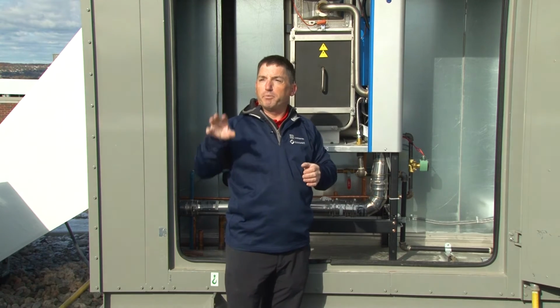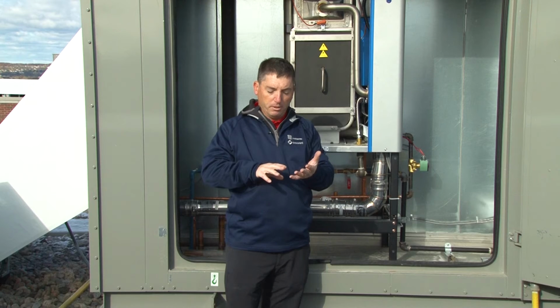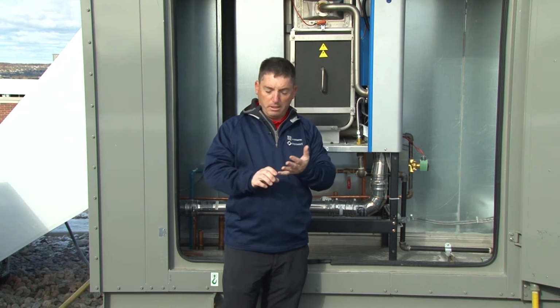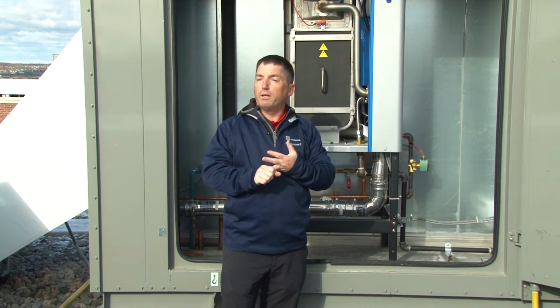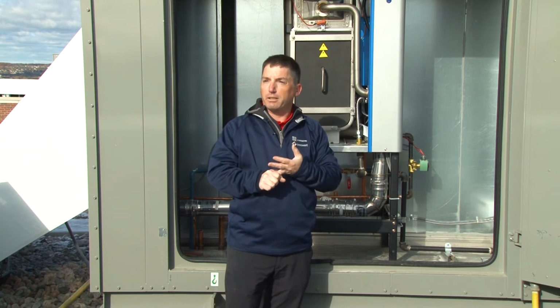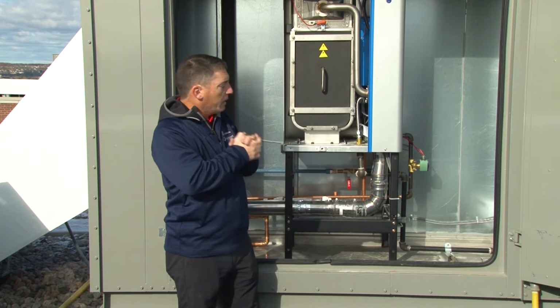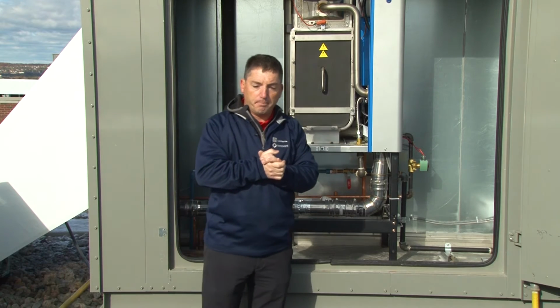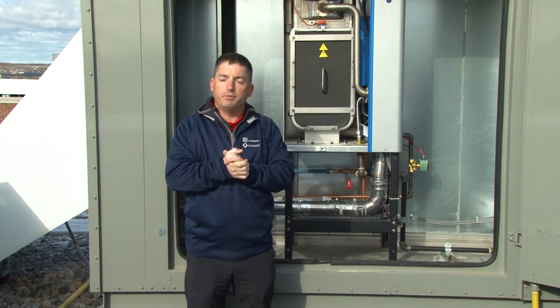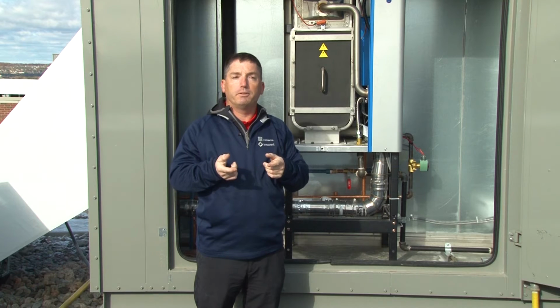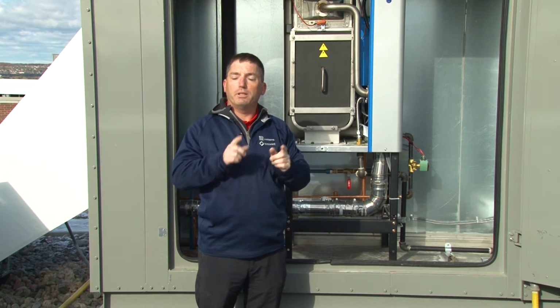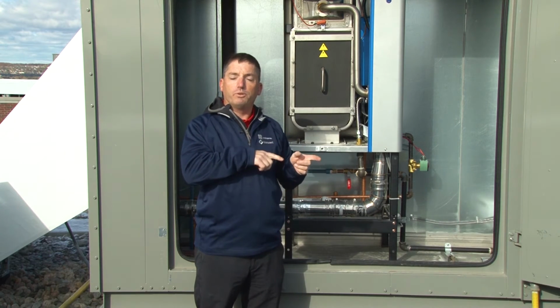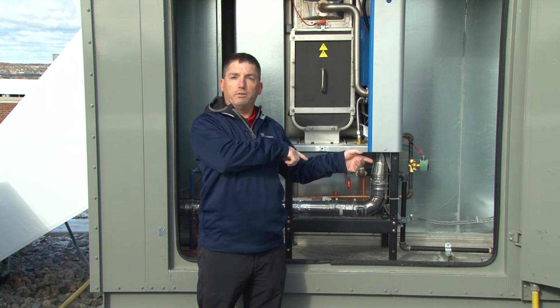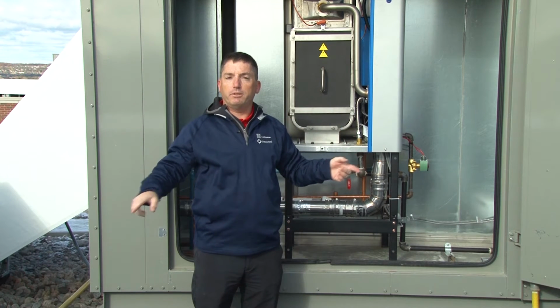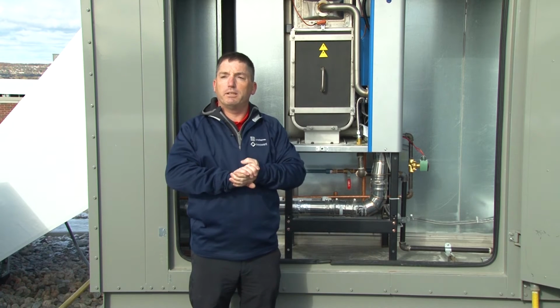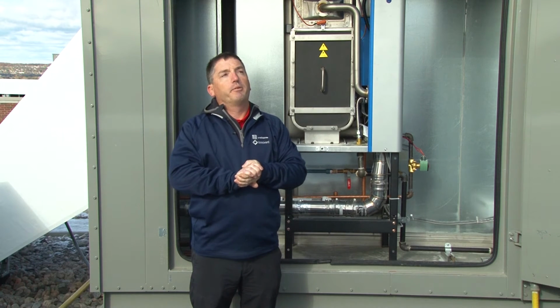It's actually going to bring up the full written description of what the code means and what possible remedies are for fixing that code. The gas unit does have internal timers, if you will. So after a couple hundred hours, it's going to close a contact which will send a signal to the keypad downstairs. What it wants is, I forget what they call it.